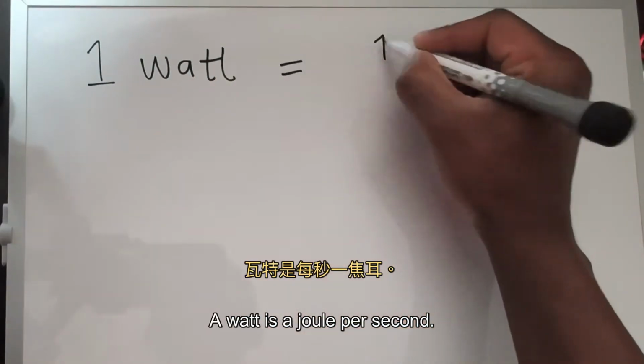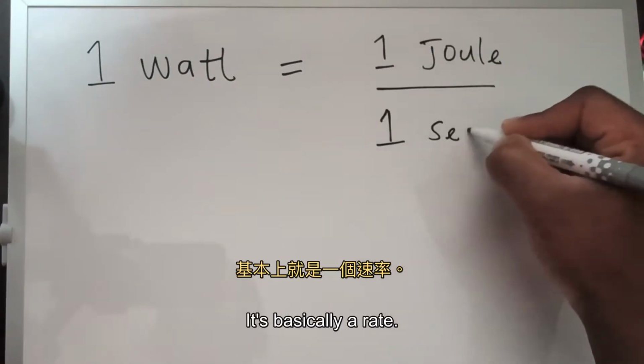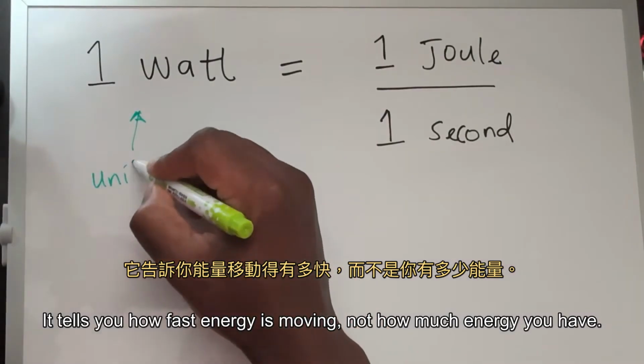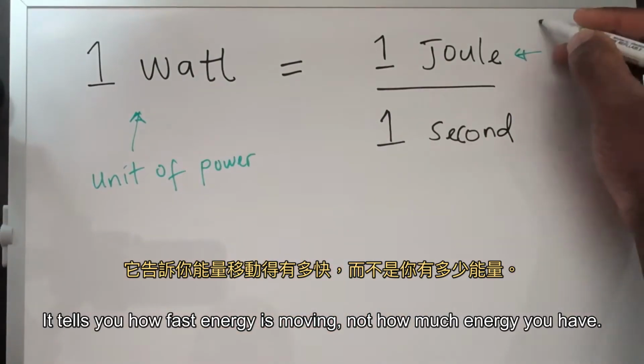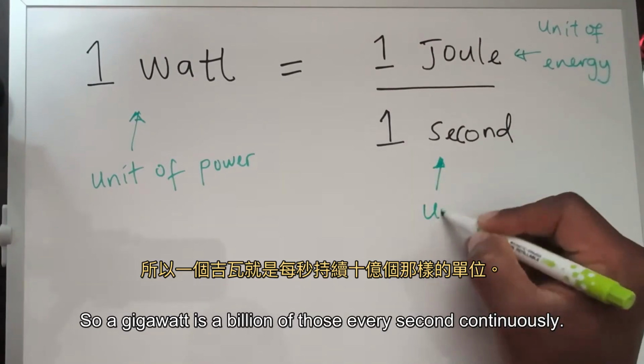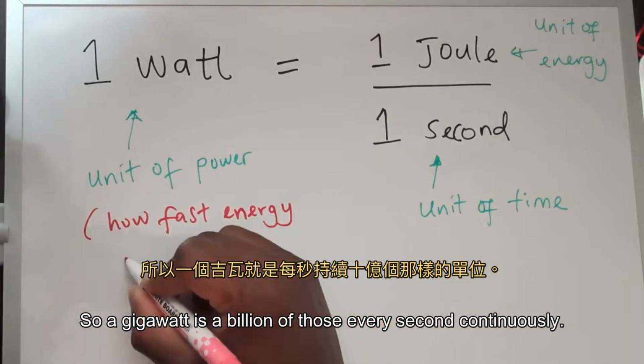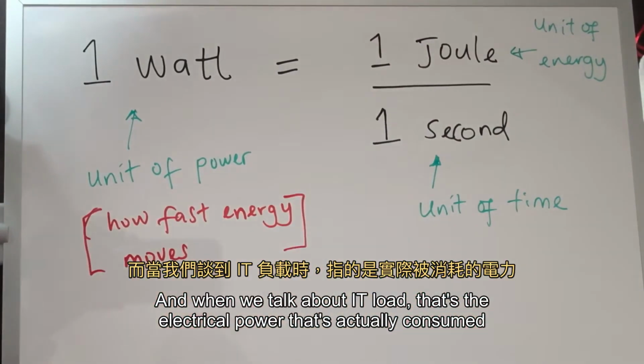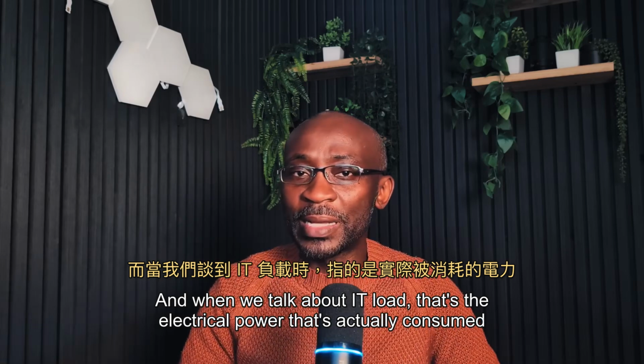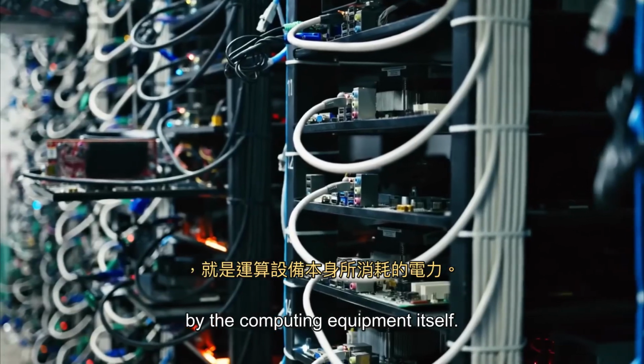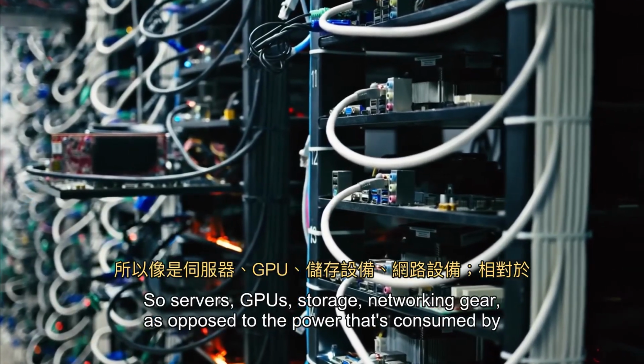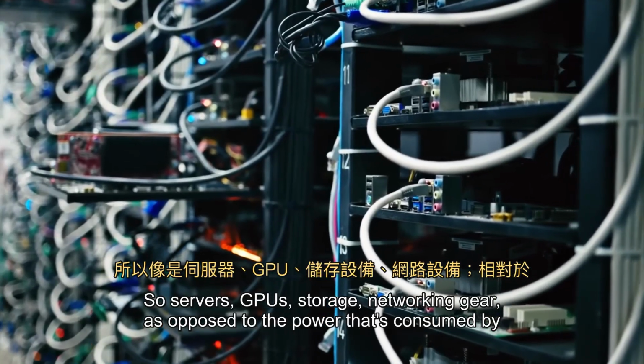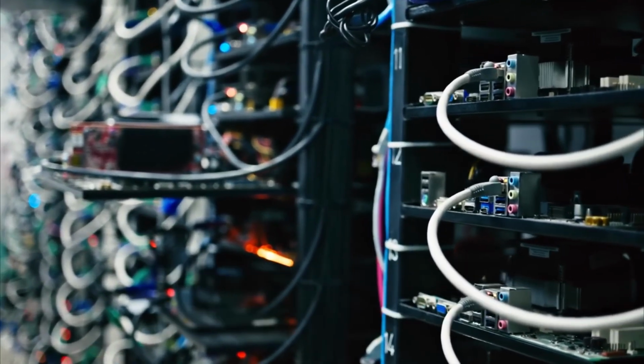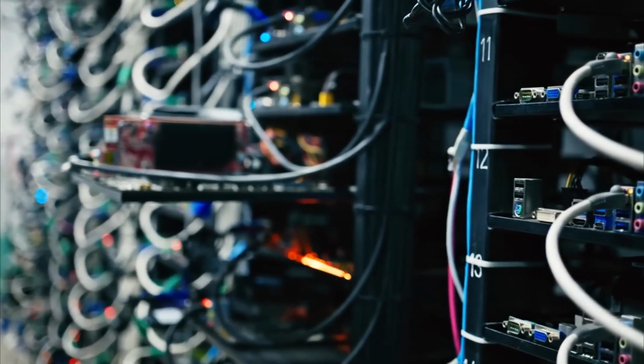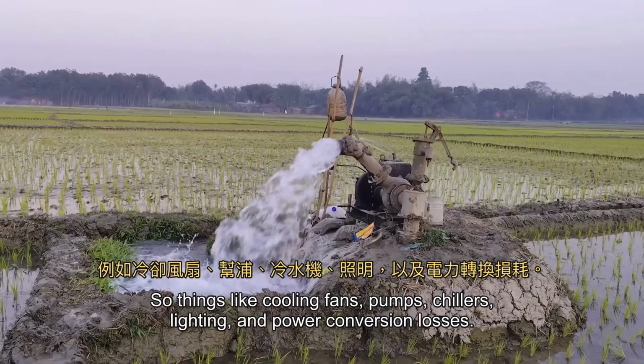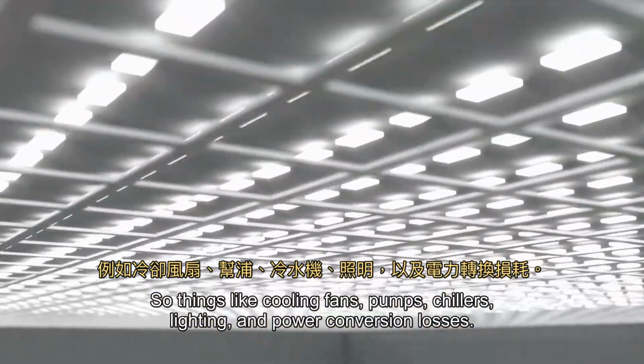A watt is a joule per second. It's basically a rate. It tells you how fast energy is moving, not how much energy you have. So a gigawatt is a billion of those every second continuously. And when we talk about IT load, that's the electrical power that's actually consumed by the computing equipment itself. So servers, GPUs, storage, networking gear, as opposed to the power that's consumed by everything else that keeps the building running. So things like cooling fans, pumps, chillers, lighting, and power conversion losses.